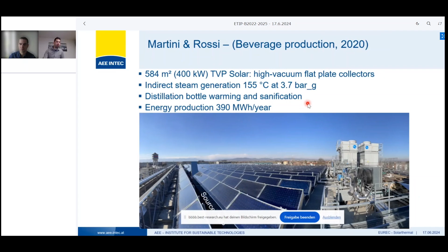A second example is a bit older, three years, but still very relevant. It has been mentioned even today: around a 400 kilowatt system by TVP, also an Italian-European manufacturer, using high vacuum flat plate collectors that can achieve quite high temperatures, 155 degrees in this case, at higher pressure. There's indirect steam generation, so the solar system actually produces hot water, but a steam heat exchanger can provide steam to the sanification, sterilization, and bottle warming processes. It was a very good example showing what non-concentrating collectors can do at higher temperatures.